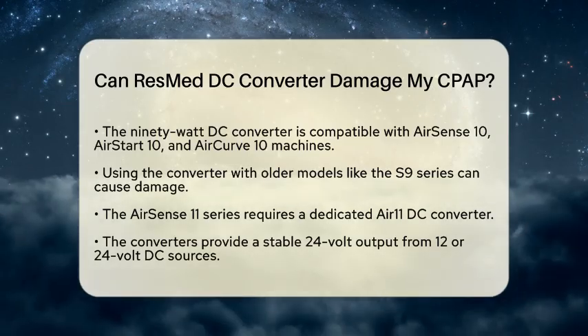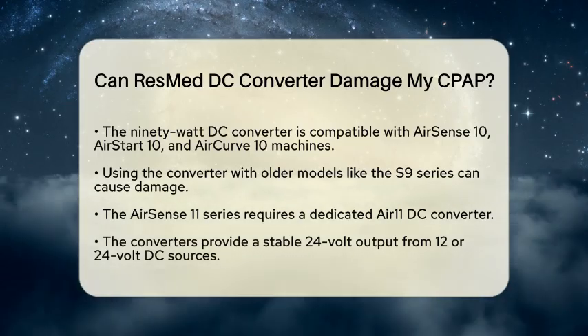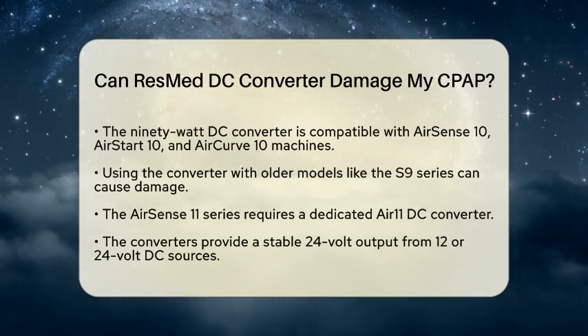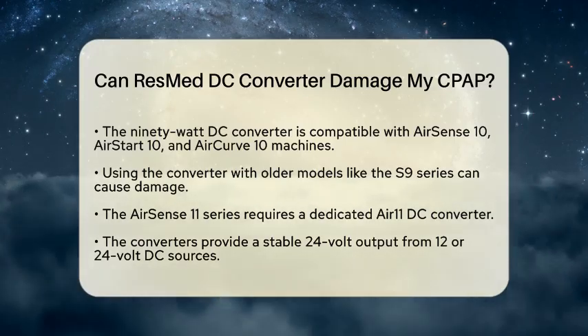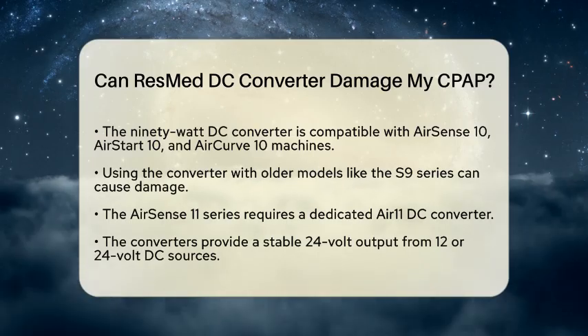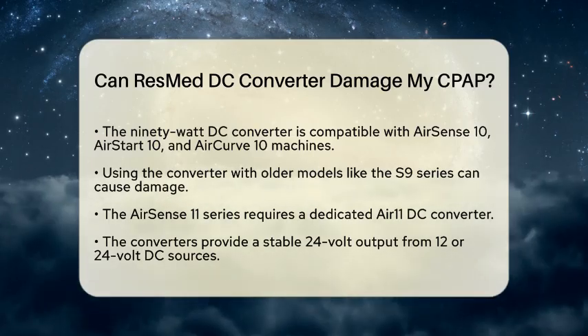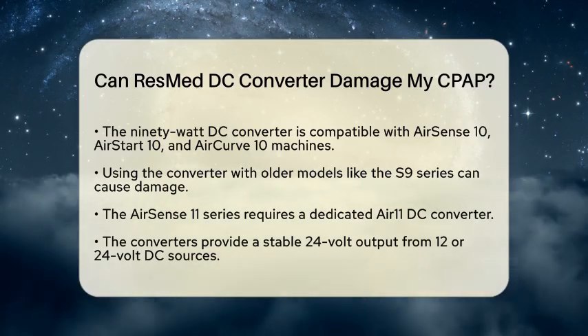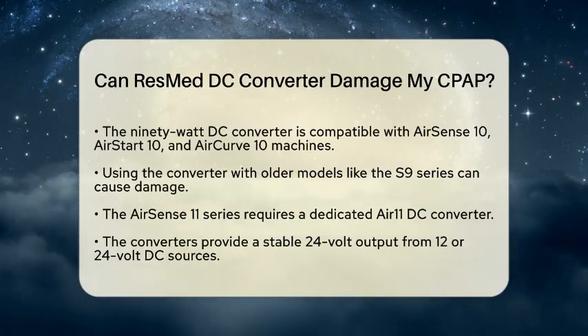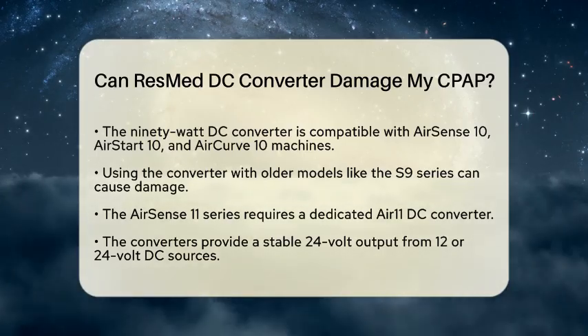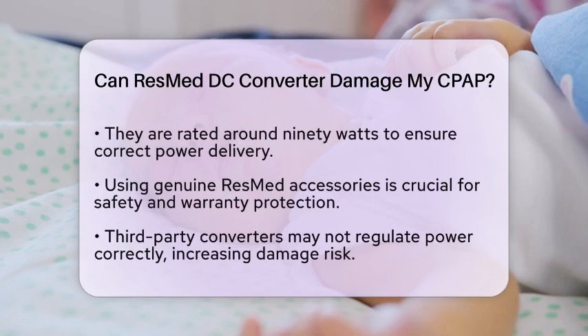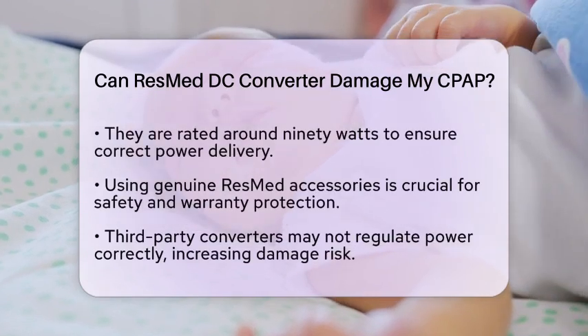Next, let's talk about voltage and power ratings. The converters provide a stable 24-volt output from 12 or 24-volt DC sources and are rated around 90 watts. This ensures that your CPAP machine receives the correct power without any fluctuations that could potentially harm its internal components.